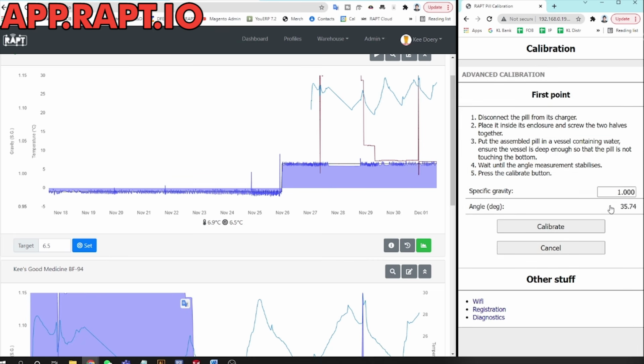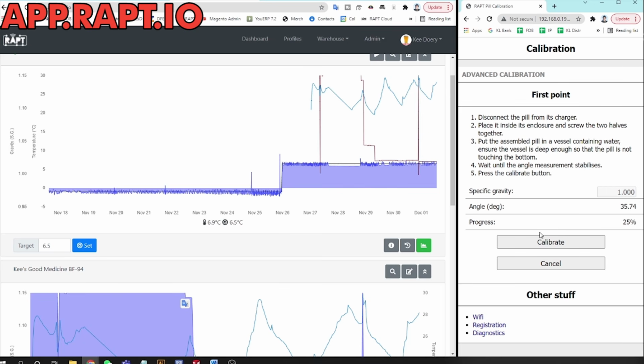Now, what it's going to do is essentially the same process, but it's going to do it twice. I've still got the pill sitting in a jug of water, as you can see here. I know that jug of water is just tap water, so the gravity is 1.000, and the angle there is just starting to stabilize. It's pretty much stable. It's varying by just a couple of points now. So look, I'm just going to hit calibrate now. And then it will take you into a second step, a 2-point calibration.